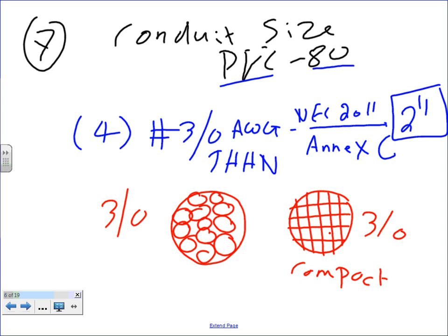No, they're not solid. They're stranded conductors. All these are strands. They just design them differently. They compact them. They're not round, so they design them differently. They use it for retrofit, so you don't tear down your conduit system.